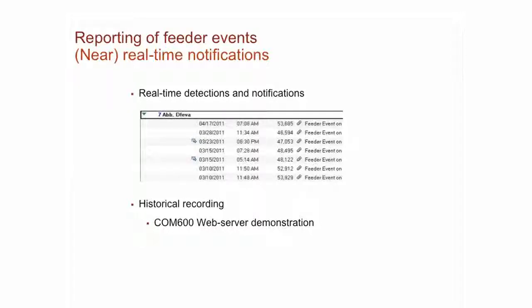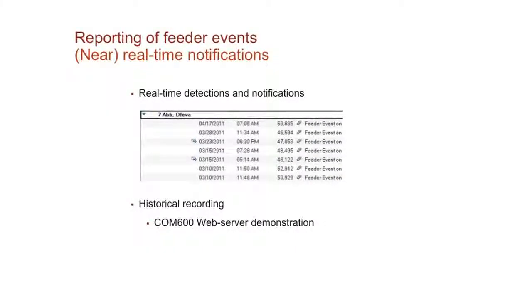You can do all kinds of historical reading and recording in that station computer, so in a given year you can just go out to it and see on a web server page all the activity on all the feeders you're monitoring, getting a good history. That can help the O&M, operation and maintenance, determine the best cables to replace for the next budget year. They may have their own list - what do you think they're primarily using? Age, exactly right. But with this information, they may learn there was a bad splice on a new cable, and they'll push that up in the priority list. This is the kind of value-added, intelligent decisions they can make with this information.